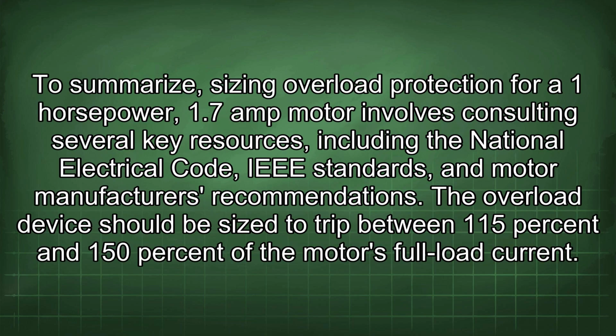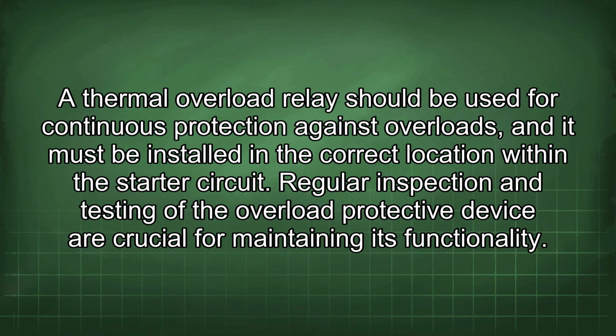To summarize, sizing overload protection for a 1 horsepower, 1.7 amp motor involves consulting several key sources, including the National Electrical Code, IEEE standards, and motor manufacturers' recommendations. The overload device should be sized to trip between 115% and 150% of the motor's full load current. A thermal overload relay should be used for continuous protection against overloads, and it must be installed in the correct location within the starter circuit.